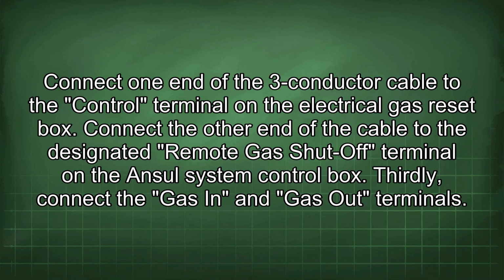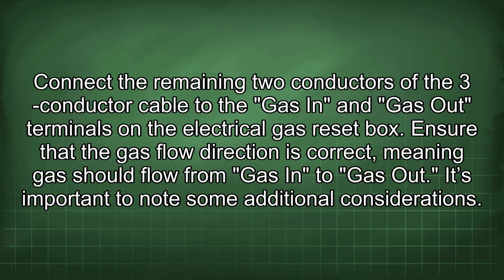Thirdly, connect the gas in and gas out terminals. Connect the remaining 2 conductors of the 3-conductor cable to the gas in and gas out terminals on the electrical gas reset box. Ensure that the gas flow direction is correct, meaning gas should flow from gas in to gas out. It's important to note some additional considerations.